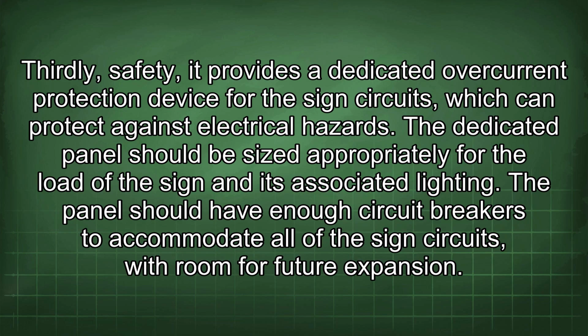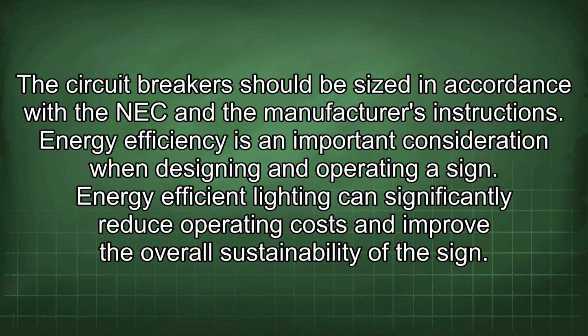Thirdly, safety: it provides a dedicated overcurrent protection device for the sign circuits, which can protect against electrical hazards. The dedicated panel should be sized appropriately for the load of the sign and its associated lighting. The panel should have enough circuit breakers to accommodate all of the sign circuits, with room for future expansion.